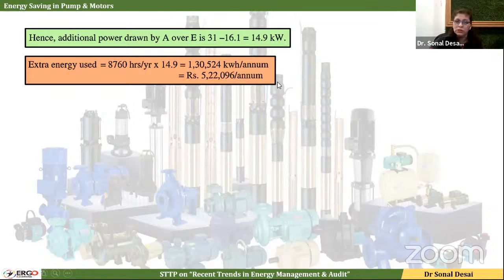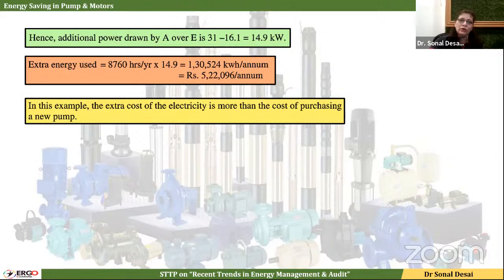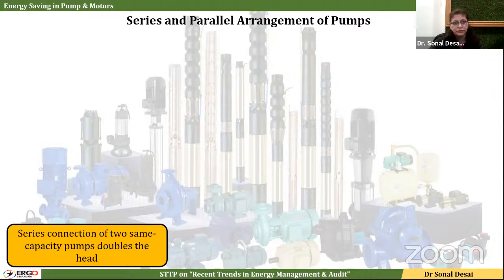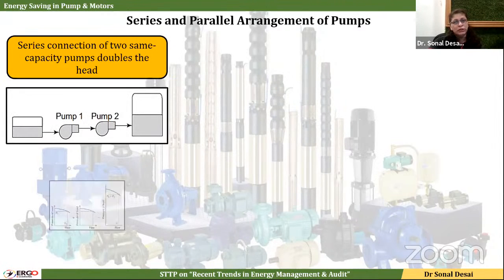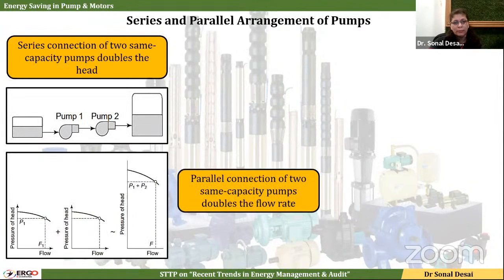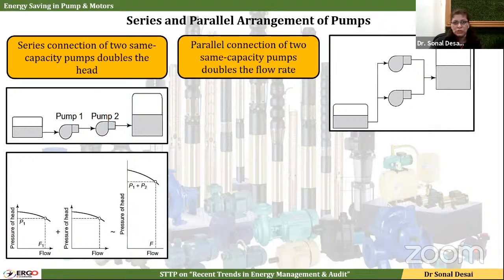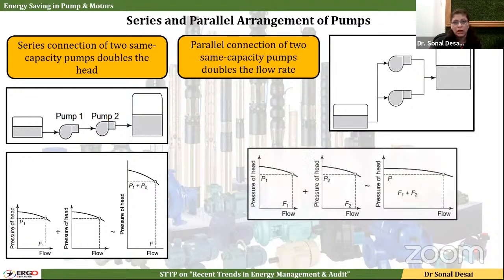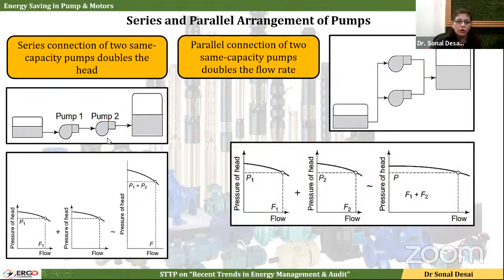So whenever there is an oversized pump, if you don't throw that pump, just disconnect it and go with the new pump. Then again, payback will be achieved and your selection will be proved, and vice versa. Another arrangement to save energy is to go with series or parallel connections rather than one large pump. It is always better. So when you are looking for more head, arrange them in series, or when you are looking for more flow, arrange them in parallel connection.